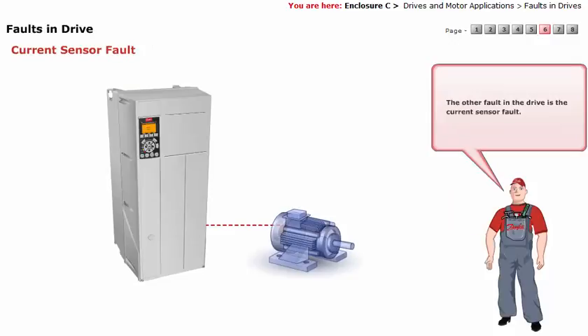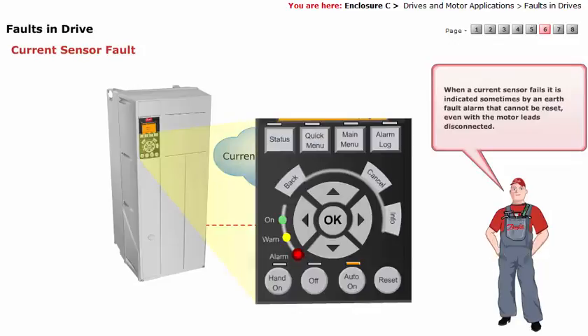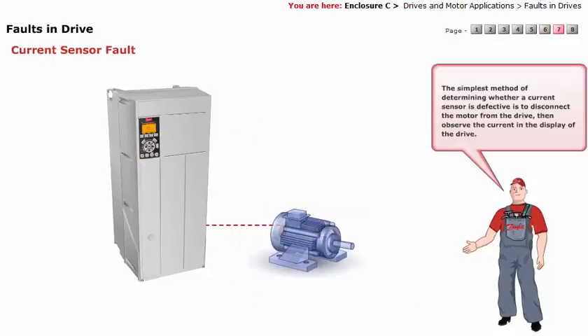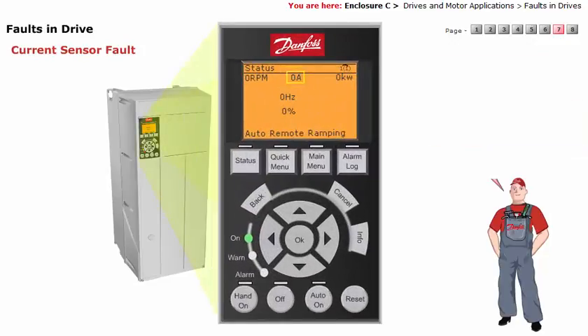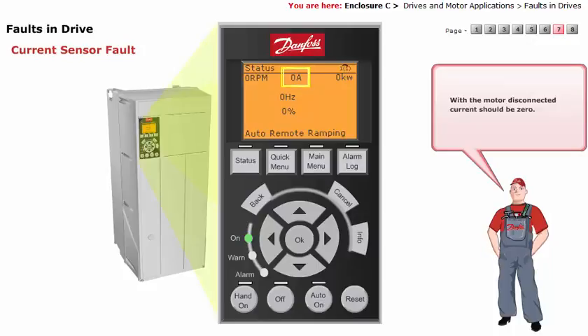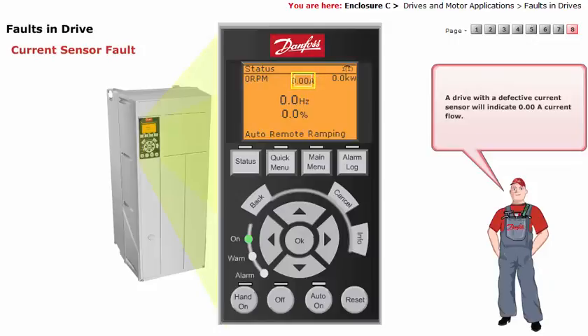The other fault in the drive is the current sensor fault. When a current sensor fails, it is sometimes indicated by an earth fault alarm that cannot be reset, even with the motor leads disconnected. The simplest method of determining whether a current sensor is defective is to disconnect the motor from the drive, then observe the current in the display of the drive. With the motor disconnected, current should be zero. A drive with a defective current sensor will indicate 0.00 amps current flow.